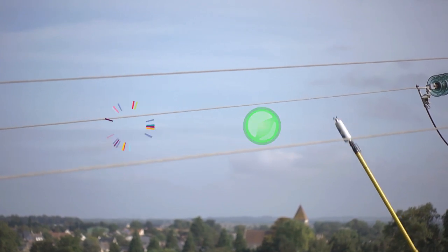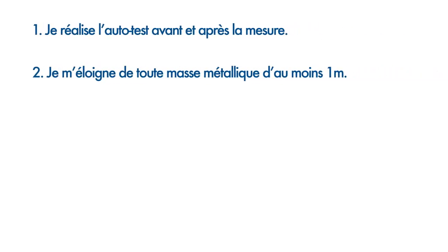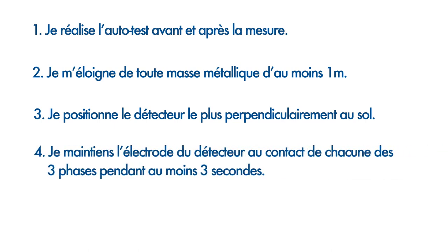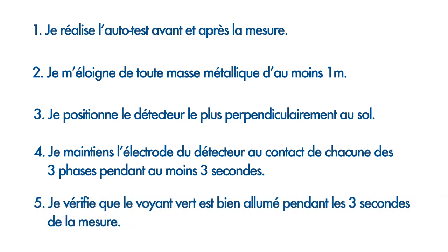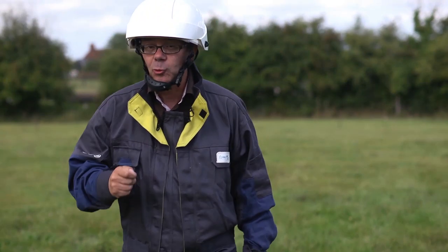In summary, to perform a good VAT: I do the auto-test before and after the measure. I stay at least 1 m away from the metallic mass. I position the detector as perpendicularly to the ground as possible. I maintain the detector in contact with each of the 3 phases for at least 3 seconds and verify that the indicator light is on during those 3 seconds. But this is not all, because there are also particular cases that I invite you to discover together.